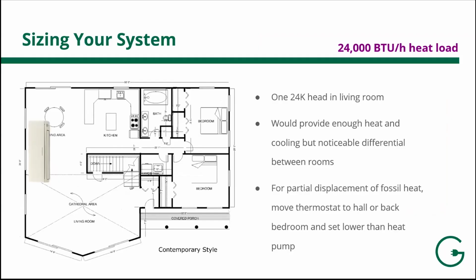The heat load for this contemporary style home is 24,000 BTUs, or British thermal units, of heat per hour. In this illustration, we've put one 24K head in the living room / dining area. This would provide enough heat to keep the house from freezing, similar to a wood stove. However, there would be a noticeable difference between rooms. For instance, the two bedroom areas in the back would be much colder than the main living area. This may be fine for you.